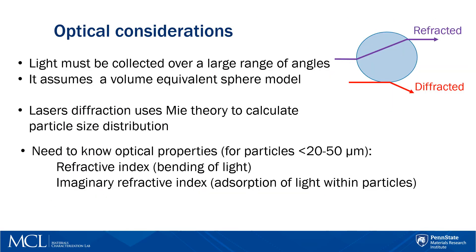There are a few considerations that must be taken into account. Light must be collected over a large range of angles. Also, laser diffraction assumes a volume equivalent sphere model, where the equivalent sphere is a sphere that diffracts light at the same angle as the particle of interest.